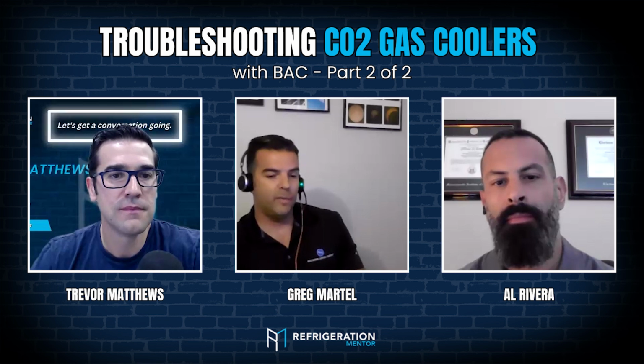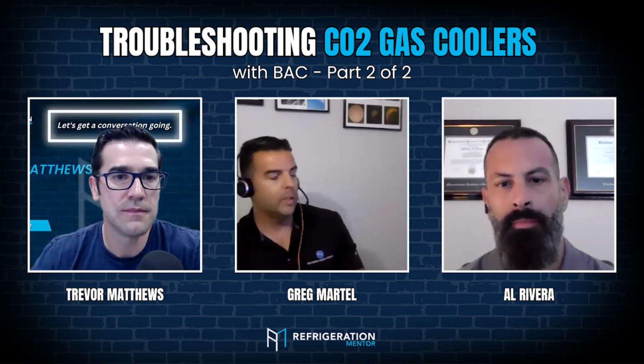And that password is needed if you wanted to make changes to the timers, or if you wanted to change how often the unit dumps and things like that. And the things that you guys were talking about before, how we control the unit. There are multiple ways you can control the fans on this unit. You can use 0 to 10, like Al was mentioning. You can also use 10 to 0. You can use 4 to 20 milliamps. You can also control it via Modbus or BACnet.